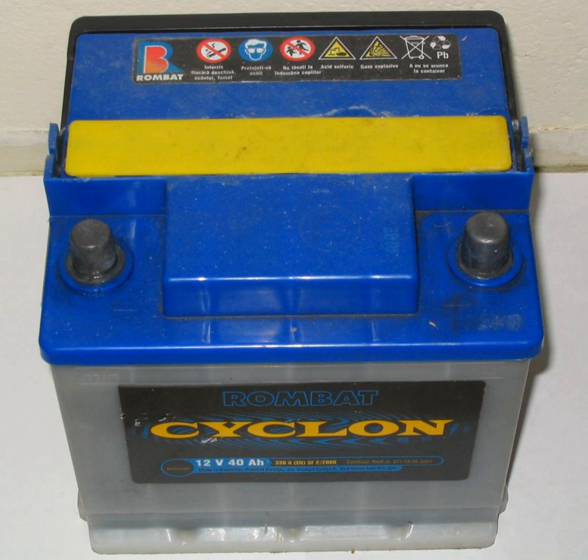The cells of VRLA batteries typically swell when the internal pressure rises, giving a warning to users and mechanics. The deformation varies from cell to cell and is greatest at the ends where the walls are unsupported by other cells. Such over-pressurized batteries should be carefully isolated and discarded. Personnel working near batteries at risk for explosion should protect their eyes and exposed skin from burns by wearing a face shield, overalls, and gloves. Using goggles instead of a face shield sacrifices safety by leaving the face exposed to possible flying acid, case or battery fragments, and heat from a potential explosion.